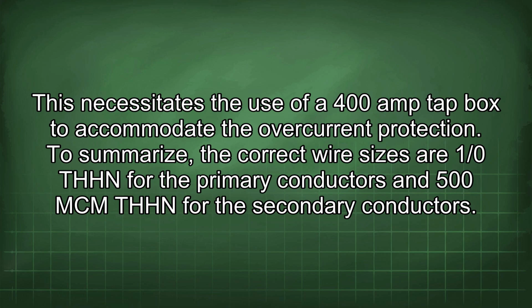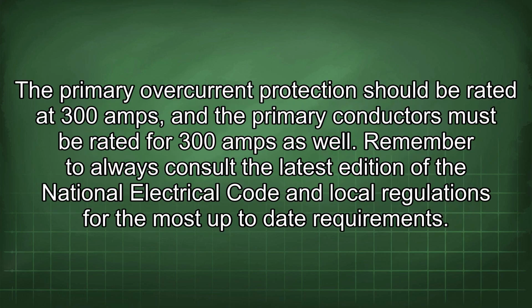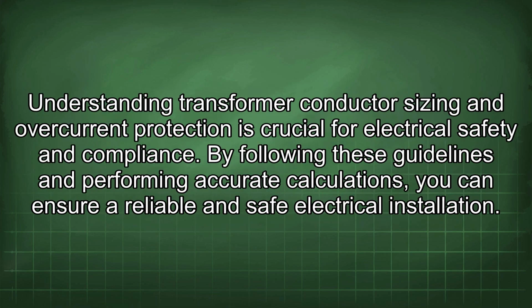To summarize, the correct wire sizes are 1/0 THHN for the primary conductors and 500 mcm THHN for the secondary conductors. The primary overcurrent protection should be rated at 300 amps, and the primary conductors must be rated for 300 amps as well. Remember to always consult the latest edition of the National Electrical Code and local regulations for the most up-to-date requirements. Understanding transformer conductor sizing and overcurrent protection is crucial for electrical safety and compliance. By following these guidelines and performing accurate calculations, you can ensure a reliable and safe electrical installation.